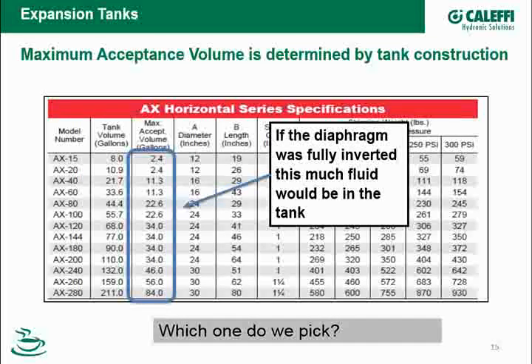Now, to get there, I may have the system go all the way up almost to the relief valve pressure. If I go large in my expansion tank, it's going to flatten out the pressure fluctuations. So I may design for a maximum pressure on my system when the system's hot of, let's call it, 25, 26 PSI. If I go large on the expansion tank, the 26 PSI may only be 17 or 18. So the real answer is, other than the added cost of the tank and possibly taking up a little bit more room in the mechanical space, I don't really see any downside of going larger with the expansion tank.